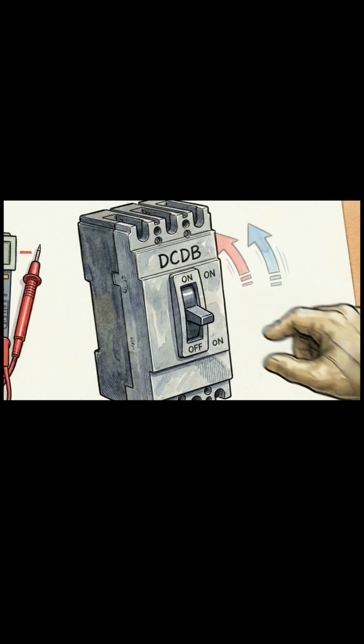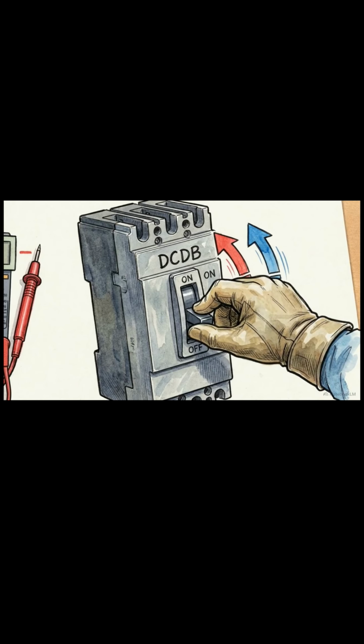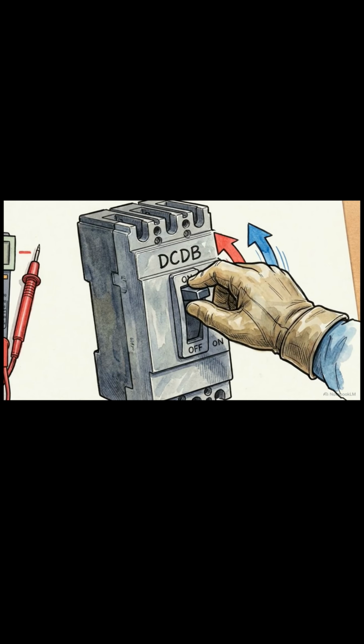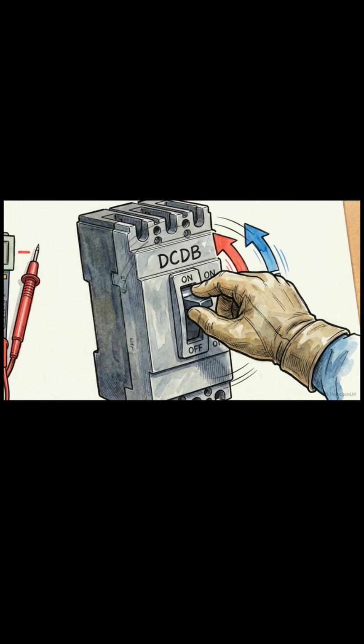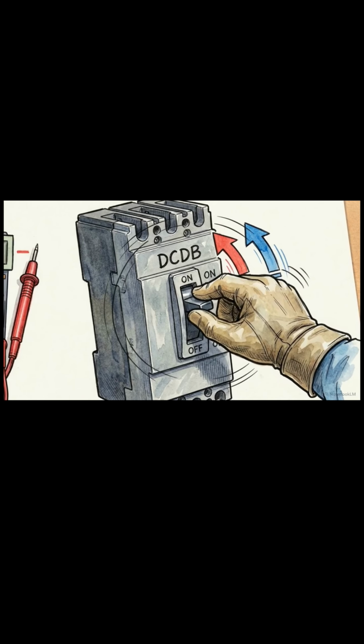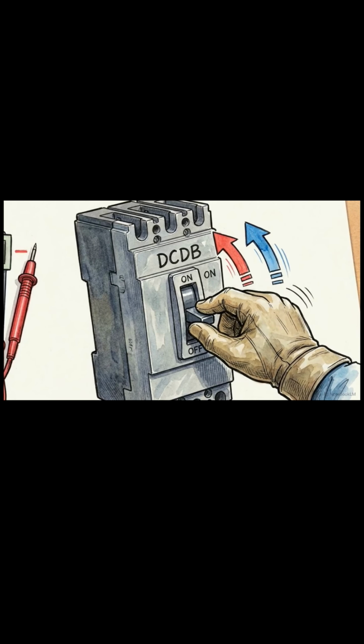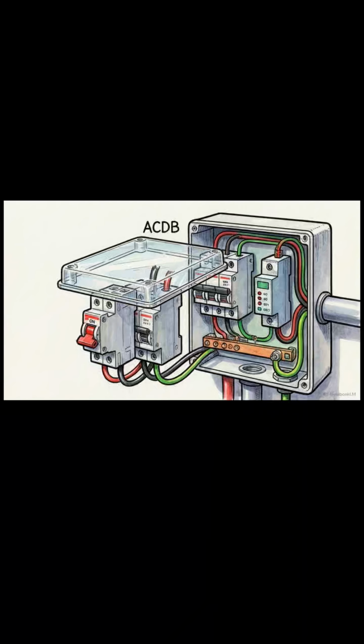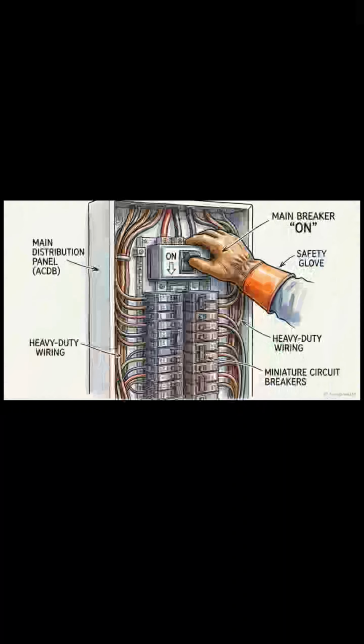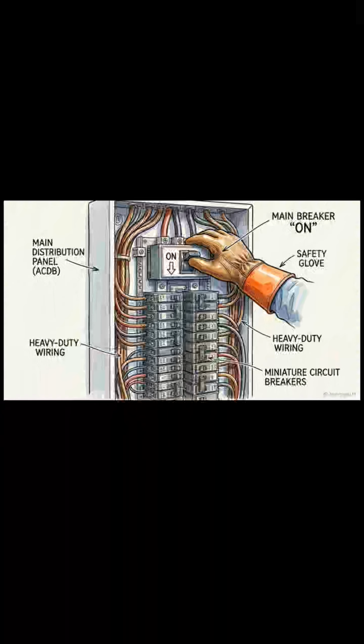It is time to energize the system, and the sequence matters. Start at the very beginning of the flow by firmly engaging the DCDB isolator. Move down the line. Flip the ACDB breaker to the on position, and finally, engage the breaker at the main distribution panel to complete the circuit to the grid.